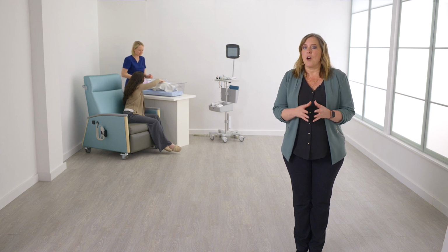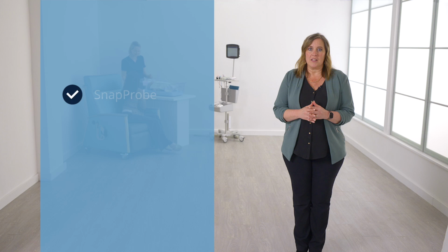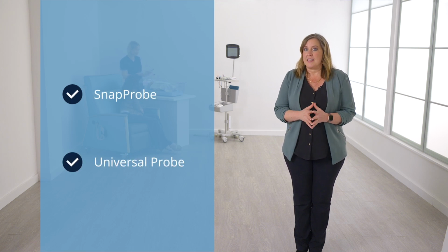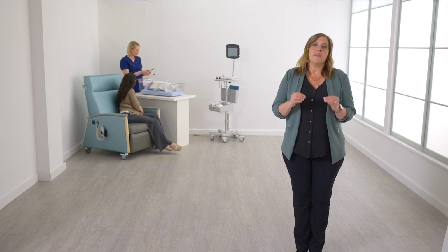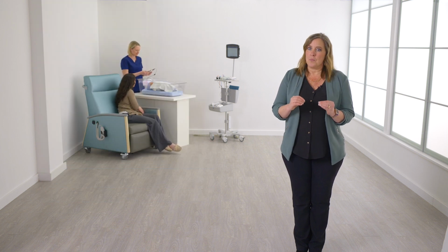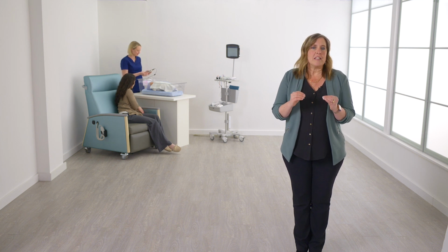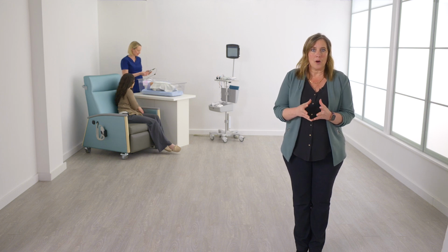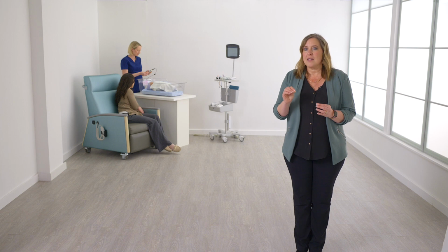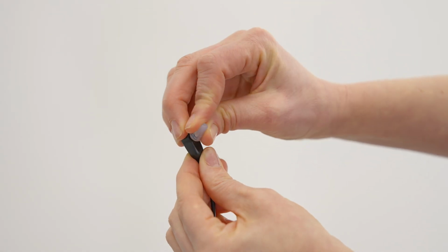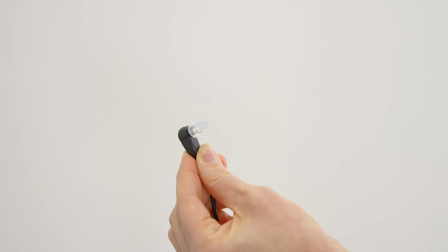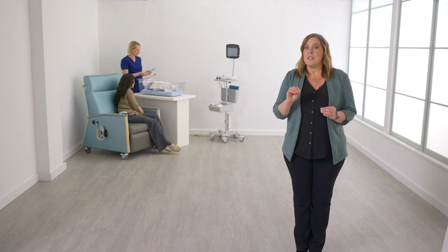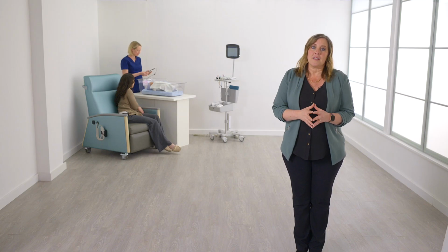There are two styles of OAE probes available with the GSI Novus, the snap probe and the universal probe. The preferred style was selected at the time of purchase. The snap probe is a specifically designed probe for infant ears. The single-use probe tips are designed to fit securely into infant ears and to prevent wax and debris from reaching the delicate electronics in the probe body. Choose the proper size snap probe infant ear tip based on your inspection of the baby's ear canals and snap it into place. If you are using the universal probe, select the appropriate size ear tip.